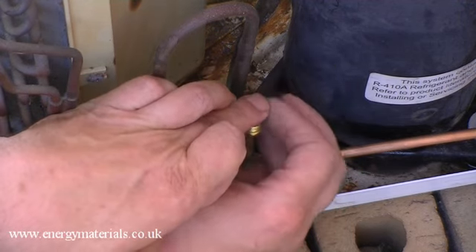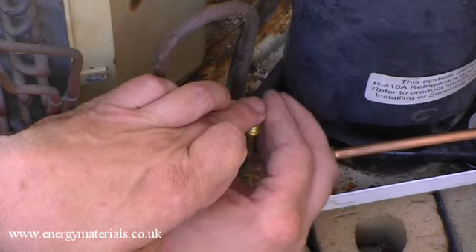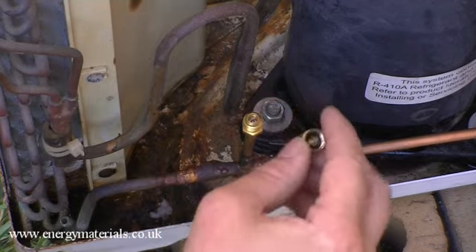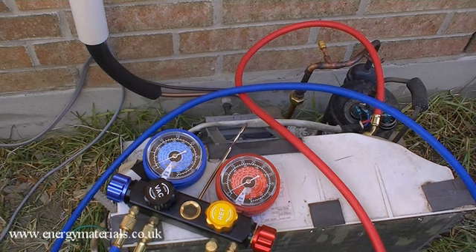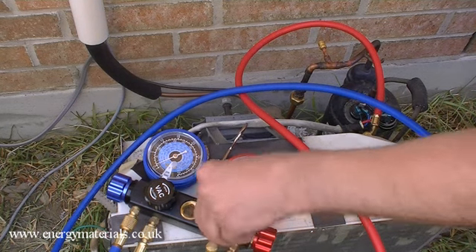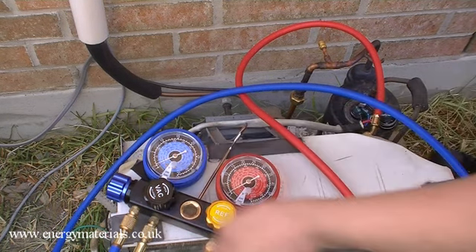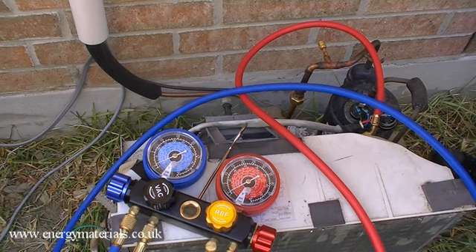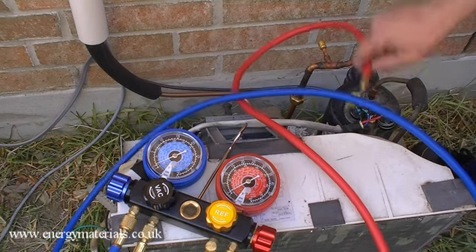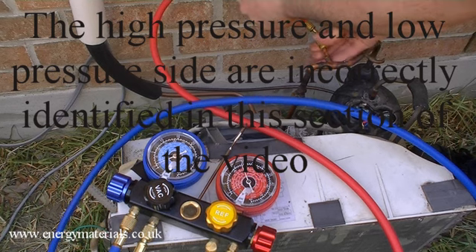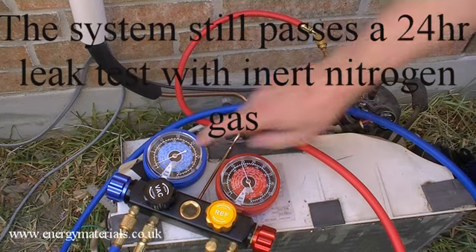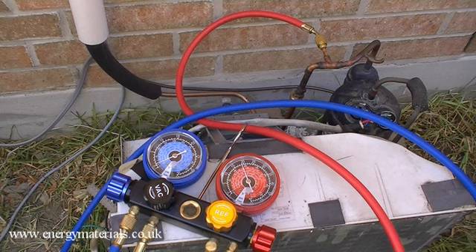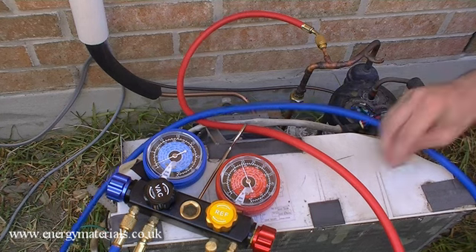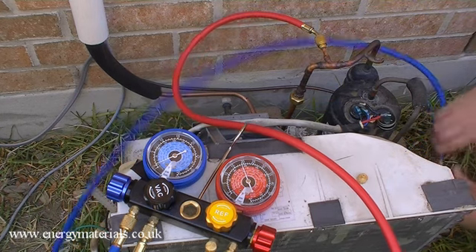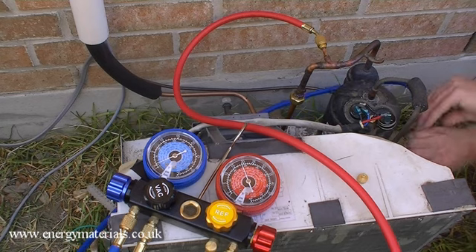So with our service valves connected, I'm now going to pressurize the entire system with 300 psi of inert nitrogen gas, and I'm going to leave it for 12 hours and see if it maintains pressure. Let's connect up our test gauges. So do the high pressure first. Screw him in. Yep, 20 bar. And we're going to try the low pressure one as well. Screwing him in now.